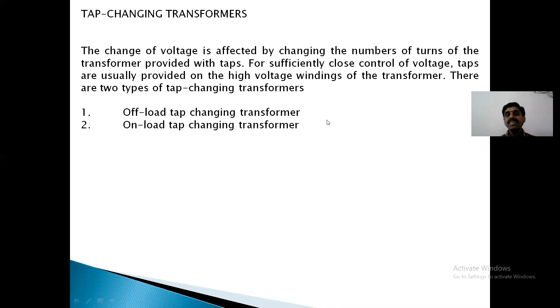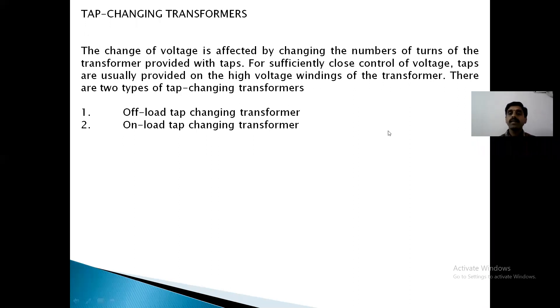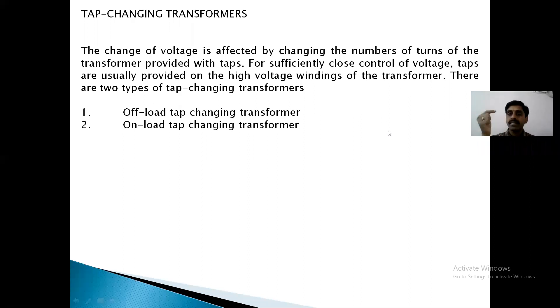These taps are generally provided on the high voltage side. Why are taps provided on the high voltage side? Because on the high voltage side, the current is less. Therefore, the current interrupted while tapping will be less. That's why taps are generally placed on the high voltage side.